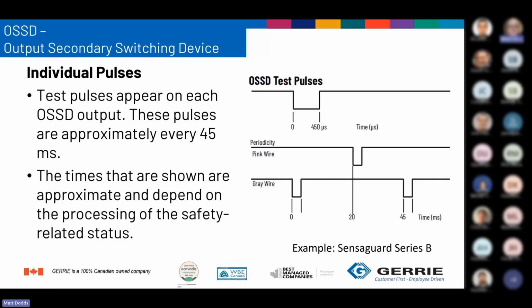So what is an OSSD, or output signal switching device? Well, an OSSD is a self-checking output that periodically turns off and looks for a backfeed voltage. In this example, if the output doesn't drop to 0 within the 450 microsecond test pulse off time, the device will go into a lockout mode and turn off both outputs.